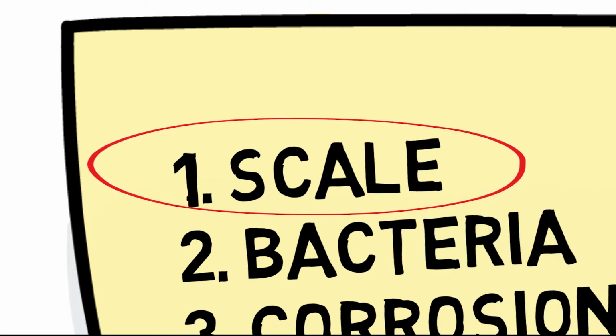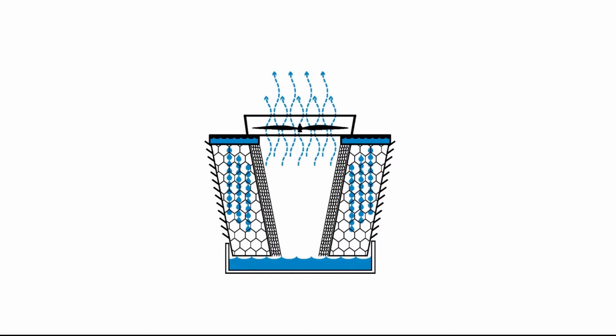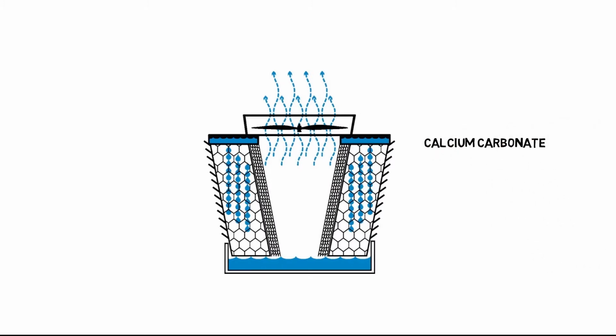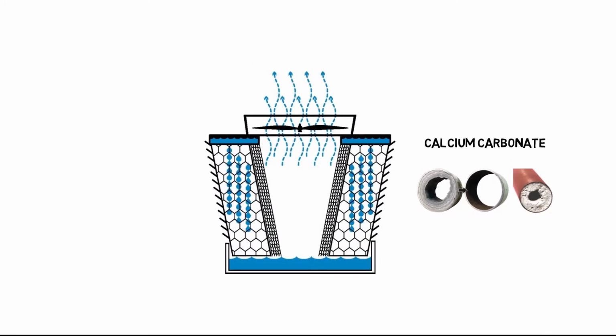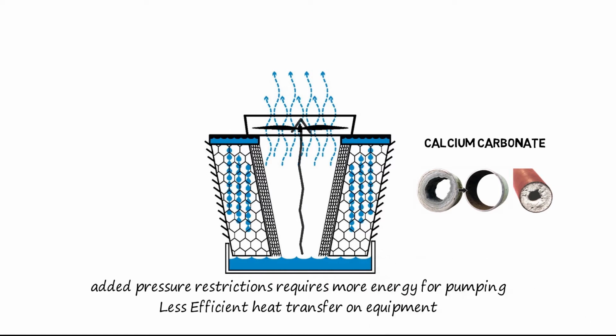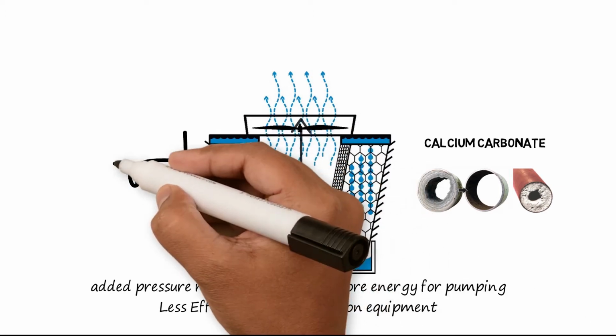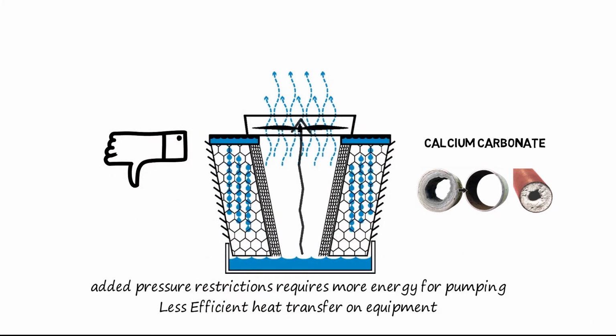To understand how the Wave effectively controls scale, let's discuss the chemistry of your condenser system. As the cooling tower evaporates water, calcium carbonate minerals become saturated and form hard limestone scale on equipment surfaces. This added restriction requires more energy for pumping, and the insulated layer makes heat transfer less efficient on heat exchangers. There is a holistic ally the Wave employs to combat scaling. It's Mother Nature. Yes, that's right.